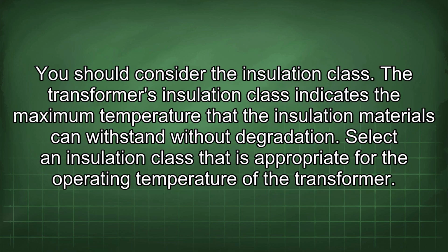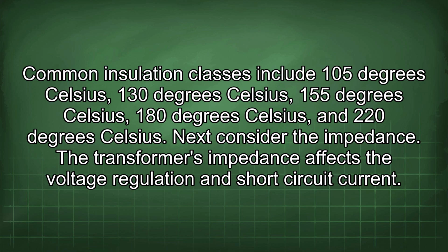You should consider the insulation class. The transformer's insulation class indicates the maximum temperature that the insulation materials can withstand without degradation. Select an insulation class that is appropriate for the operating temperature of the transformer. Common insulation classes include 105 degrees Celsius, 130 degrees Celsius, 155 degrees Celsius, 180 degrees Celsius, and 220 degrees Celsius.